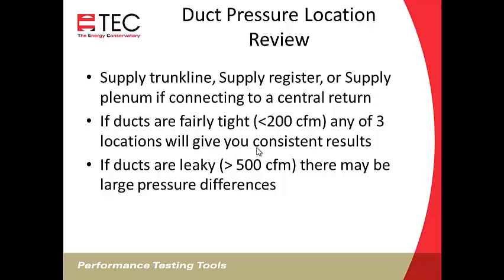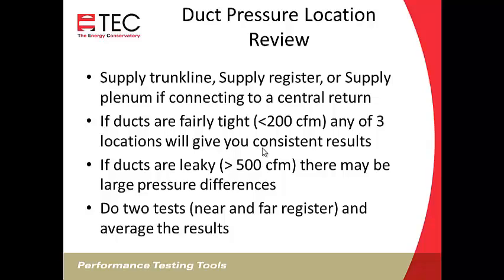What you can do is, with the Duct Blaster at 25, check the pressure at the farthest supply register and the closest supply register and see if there's much of a difference, see if it warrants that second test and averaging the results. So greater than 500, we want to do two tests, near and far register, and average the results.